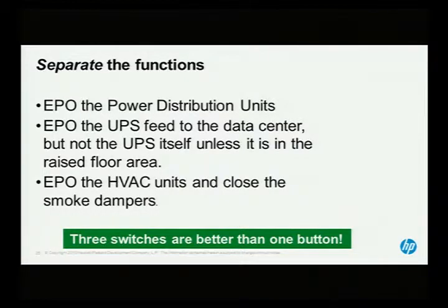Our Tier 4 data centers, can they actually statistically deliver 100% availability? Yes, for short periods of time, but over a long time they can't, because there typically are two single points of failure. One is the EPO, and the other is the ground fault systems. So this begins to address how you attack that particular single point of failure.